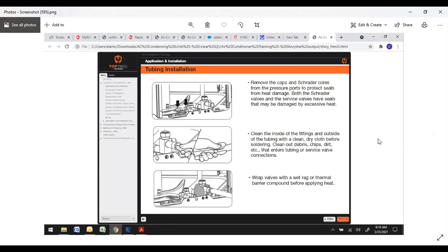So now when you are getting ready to braze, this is very important. We had a couple come back last year, valves that were leaking out of the top, and Rheem sent them to their engineers because we had two of them. One looked really, really burnt. The other one didn't. But they took them back and cut them open and verified that they were indeed cooked. So whenever you're going to do any brazing on the service valves, obviously remove your cap on top, and Schrader cores from the pressure ports to protect the seals, because they do have seals and they will melt. Both Schrader valves and service valves have seals that may, and will, be damaged by excessive heat.